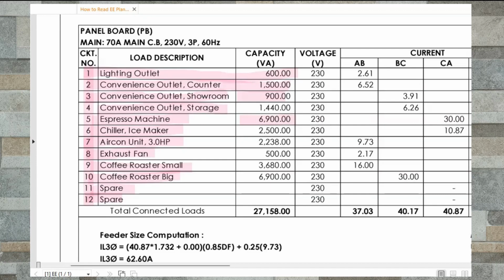So tingnan natin, binabalanse yung bawat load nito, yung 12 circuits. So binabalanse siya to determine na hindi nag-overloading yung isang leg. So if you see the total, merong 37.03 amperes sa line AB. Yung line BC, meron tayong 40.17 amperes. Yung line CA, 40.87 amperes. So di naman talaga perfectly 100% na mabalance siya. As long as meron ka lang maliit na tolerance, pwede nang sabihin na near balance yung ating load schedule. So yung kanilang gap maliit lang. Okay, so dapat ibabalanse natin para walang overloading.